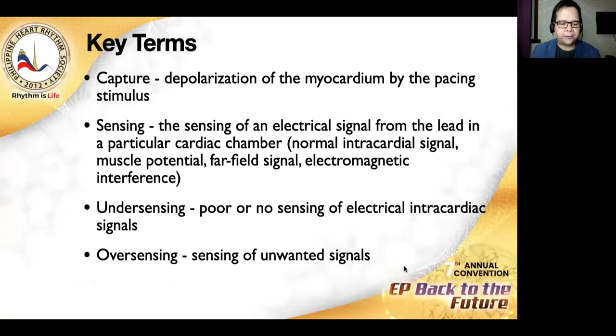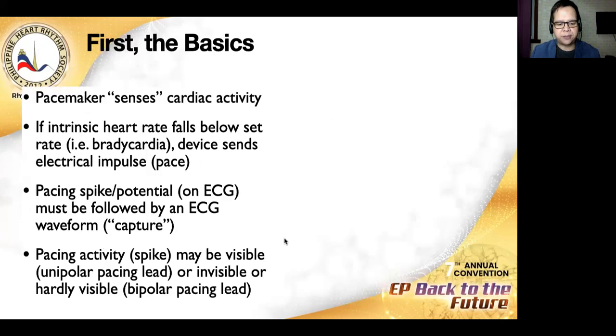Now, it is also vital that we familiarize ourselves with some of the key terms that relate to pacemaker function. Capture refers to stimulation and depolarization of the myocardium by the pacing stimulus. Sensing pertains to the ability of the pacemaker to see the electrical signal from the lead in the particular chamber. Undersensing refers to poor or absent sensing of the electrical signals, while oversensing means unwanted small signals not meant to be seen are sensed by the device.